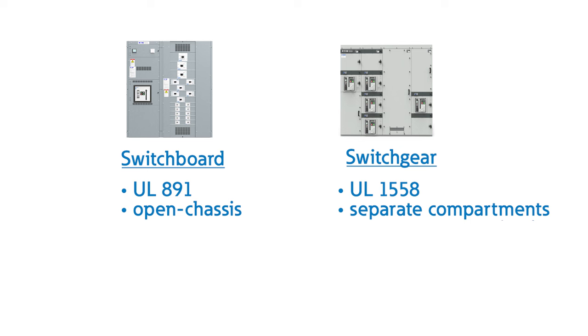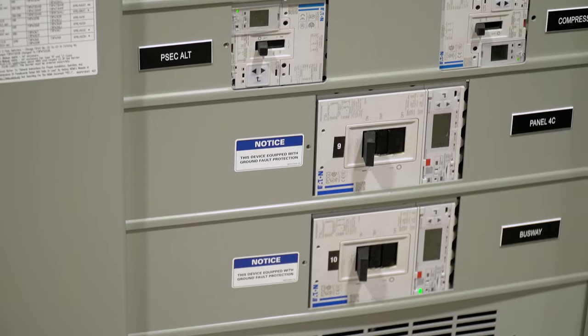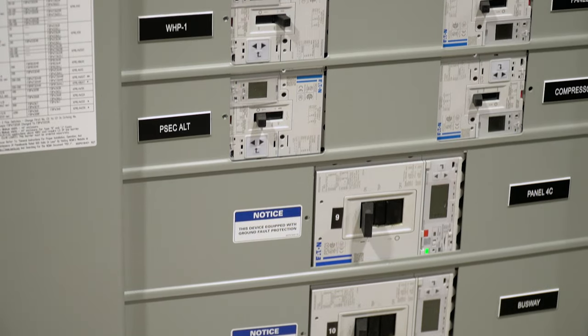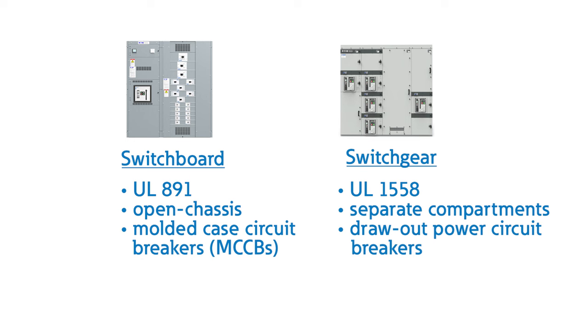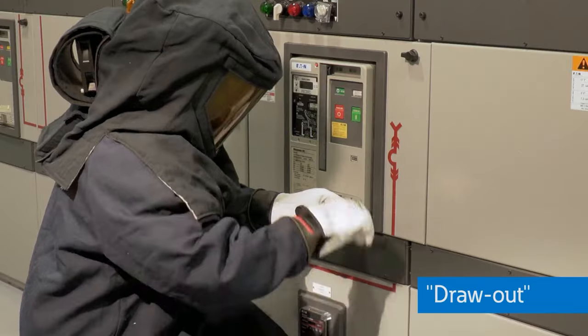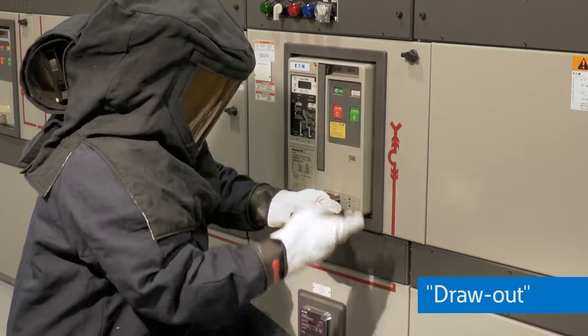Another visual difference is the type of breakers used. Switchboards will typically use fixed-mounted, molded case circuit breakers, or MCCBs, that fall under UL489. Since MCCBs can't be serviced, the entire enclosure must be de-energized before replacement of existing breakers or the addition of new breakers. On the other hand, switchgear will have draw-out power circuit breakers that can be removed and maintained without fully interrupting a power system.